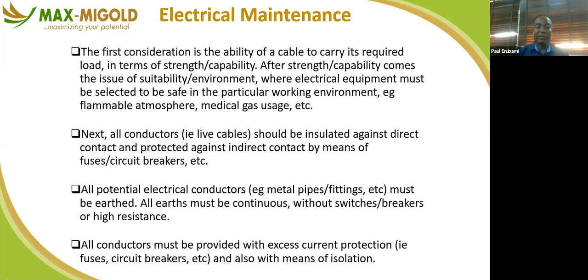So in case someone comes in contact, instead of being electrocuted, the person is saved by the breaker tripping off. So all potential electrical conductors, e.g. metal pipes and fittings, must be earthed. Like those days, we used to have this galvanized pipe used for plumbing in the toilet in the early days, but today we are making use of PVC. Because they have contact with water, there may be leakage current somewhere, and this water gets to where that leakage current is, and this leakage is conducted to the metal plate. So that's why it is advisable, if you still manage such a facility or have anything that has to do with potential conductors, you need to earth them to reduce the effects it will have on a human or whoever comes in contact with it.